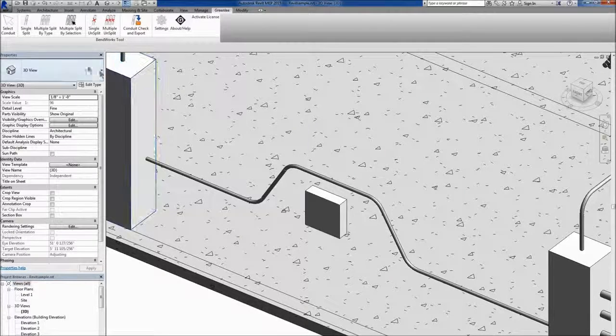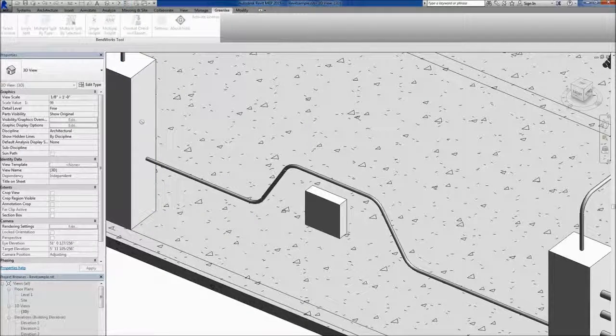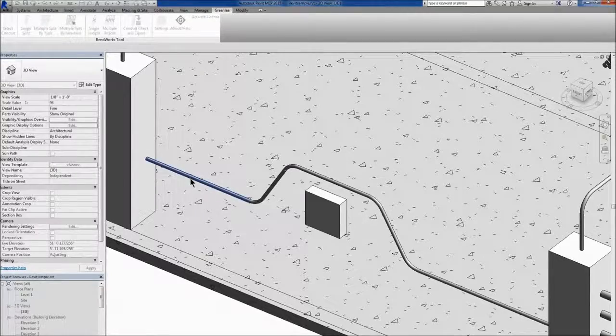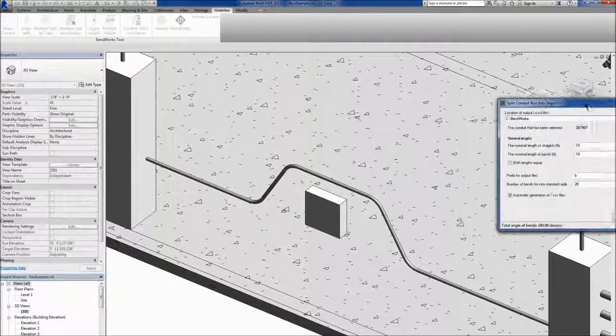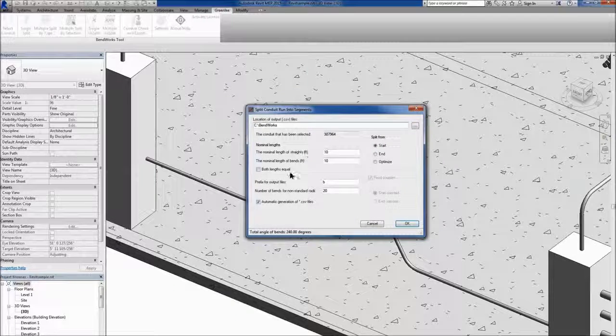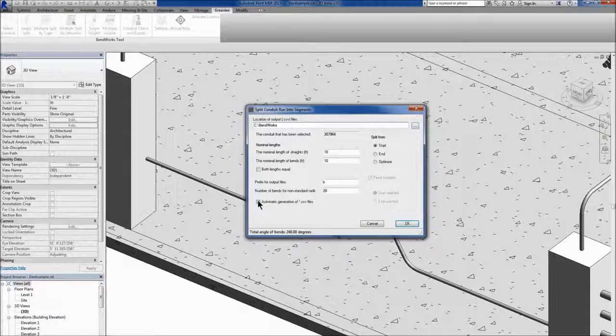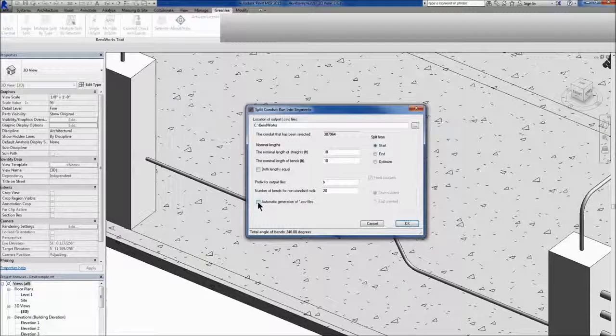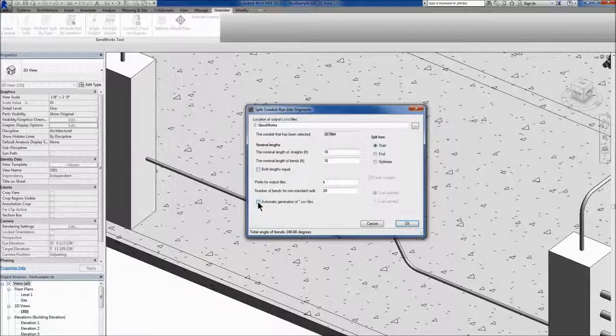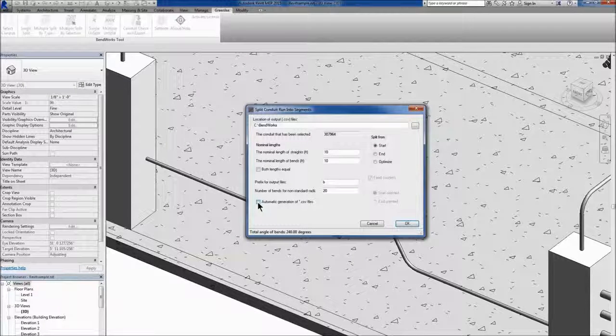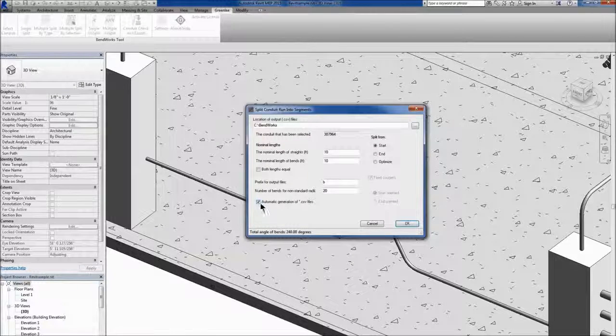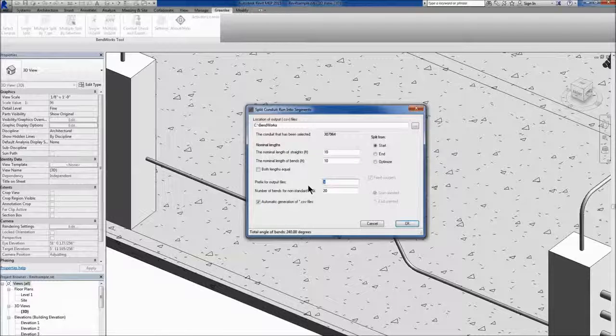Later, when splitting a run, the Split Conduit Run Into Segments dialog box allows you to deselect automatic generation of CSV files if you do not want any output files generated. To create a naming convention for a particular conduit run, you may enter up to seven characters in the Prefix for Output Files field. This will be attached with a numerical suffix to each segment and correspond to the output file of the same name.